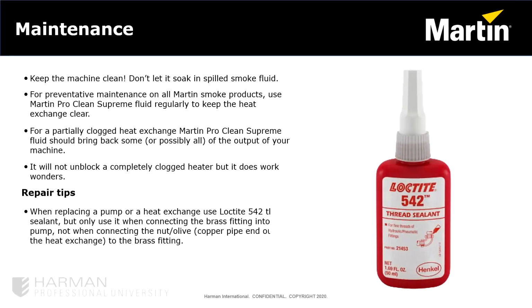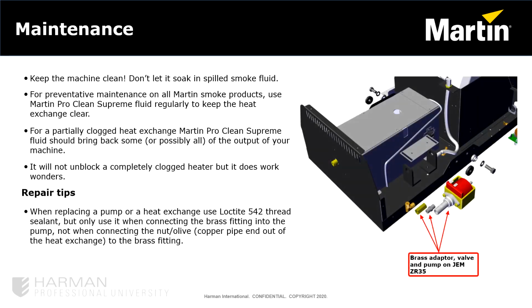The bare heater is relatively straightforward to replace. Using Loctite 542 thread sealant on the replacement of the pump or the heat exchange is very important and should be considered mandatory. Loctite should be used on the threads between the brass fitting and the plastic pump. If this is not done, over time, deterioration of the seal will occur and cause the fluid to leak, which will lead to lower output since there will be less fluid going through the heater. Also, fluid will have leaked inside the unit.